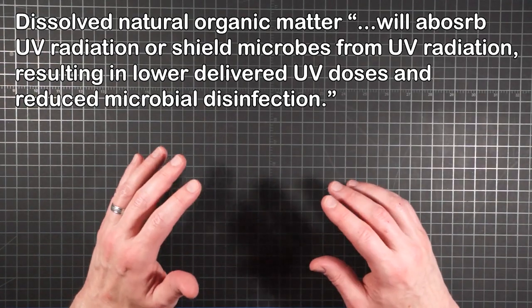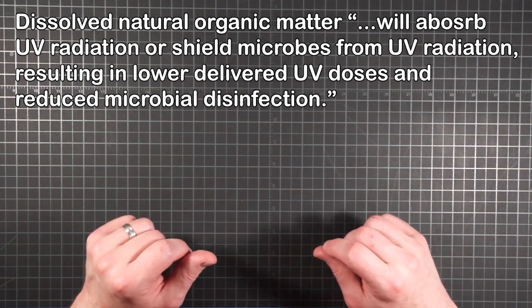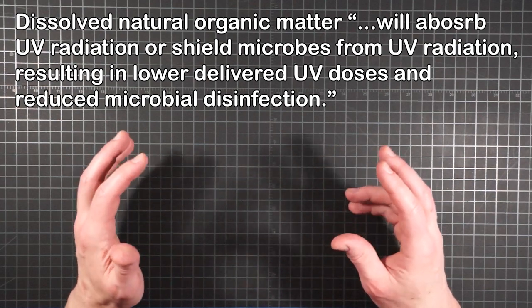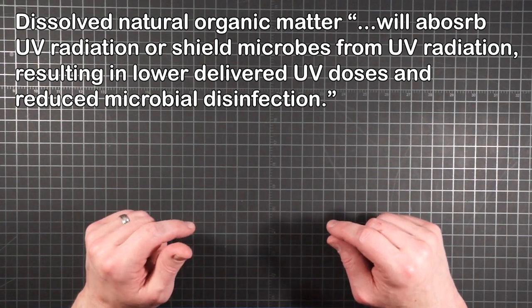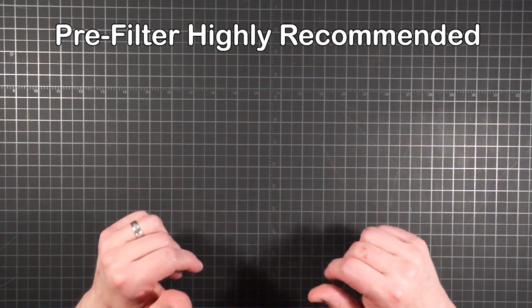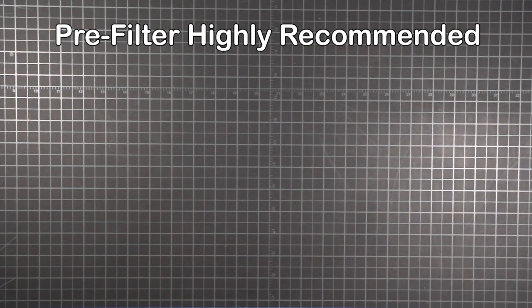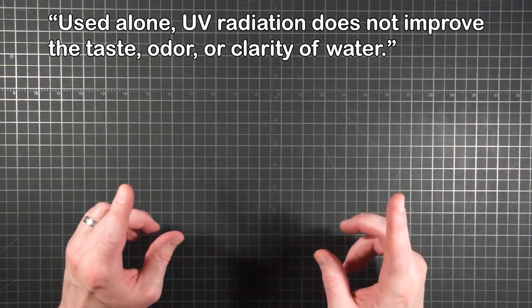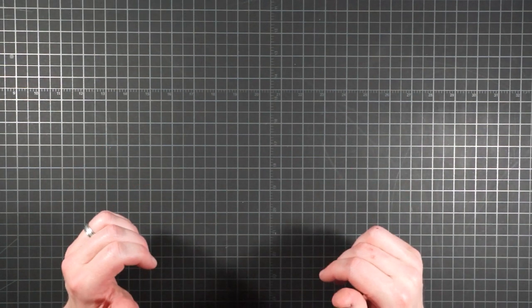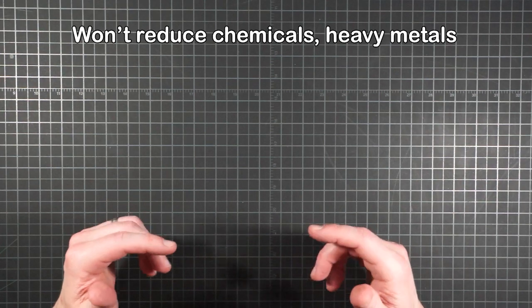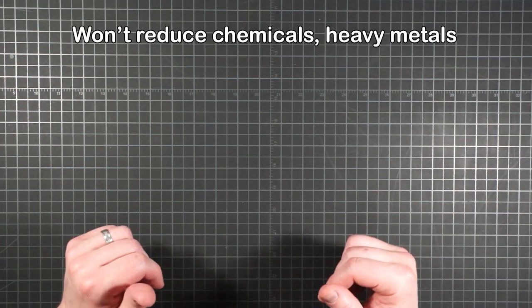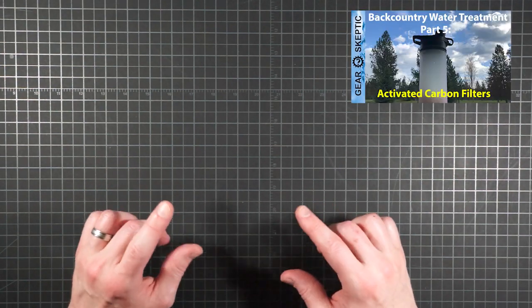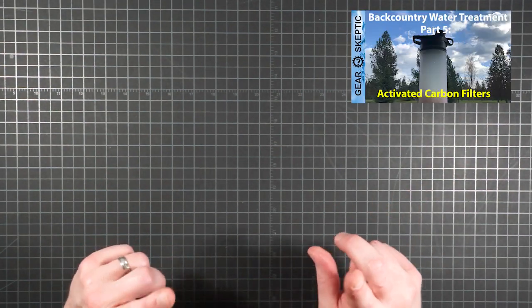Also, dissolved natural organic matter will absorb UV radiation or shield microbes from UV radiation, resulting in lower delivered UV doses and reduced microbial disinfection. Again, some sort of pre-filter is highly recommended. Used alone, UV radiation does not improve the taste, odor, or clarity of water. And since it doesn't remove anything from the water, UV won't reduce chemicals, heavy metals, or other impurities. If any of those things are a concern, consider an activated carbon or adsorption filter like those discussed in part 5.